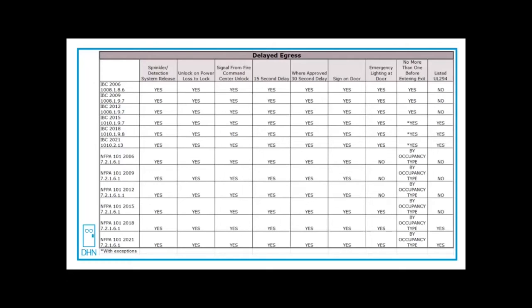The door will unlock on loss of power. It's fail safe or signal from the fire command center to unlock. Any sprinkler detection or smoke detection would unlock the door. So if there is a fire, you can get out immediately.